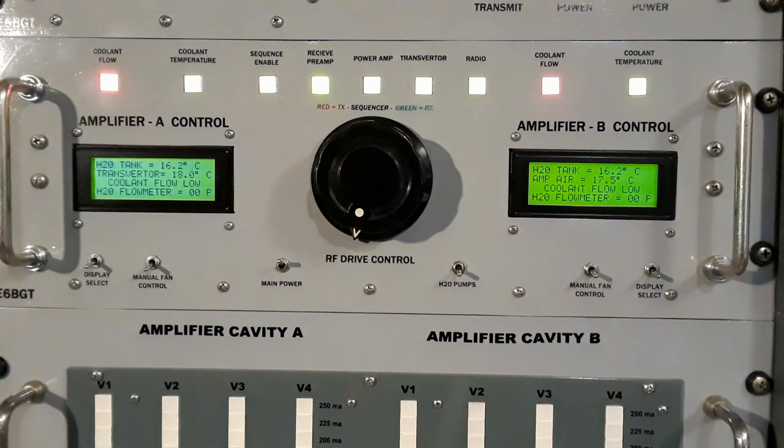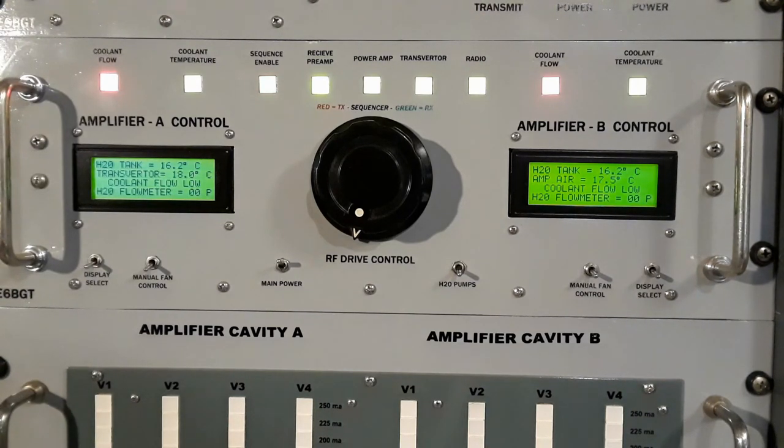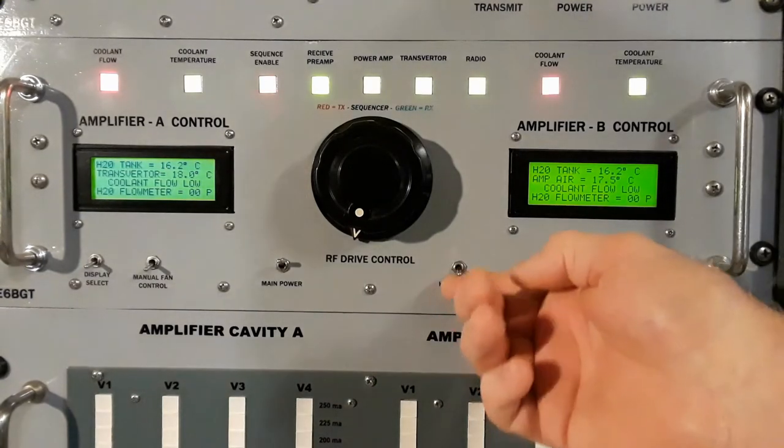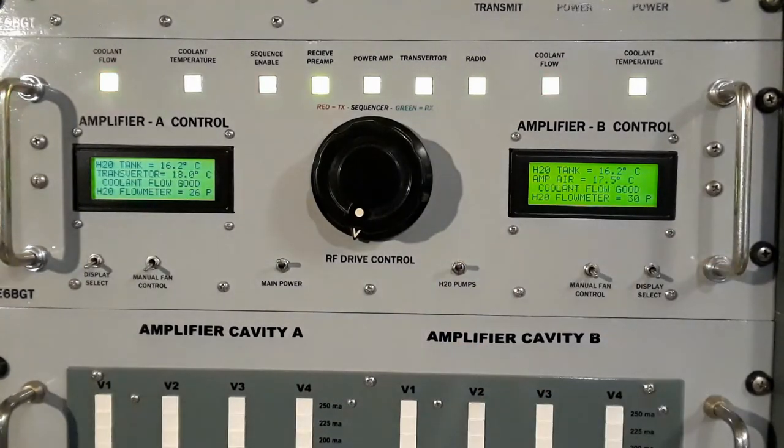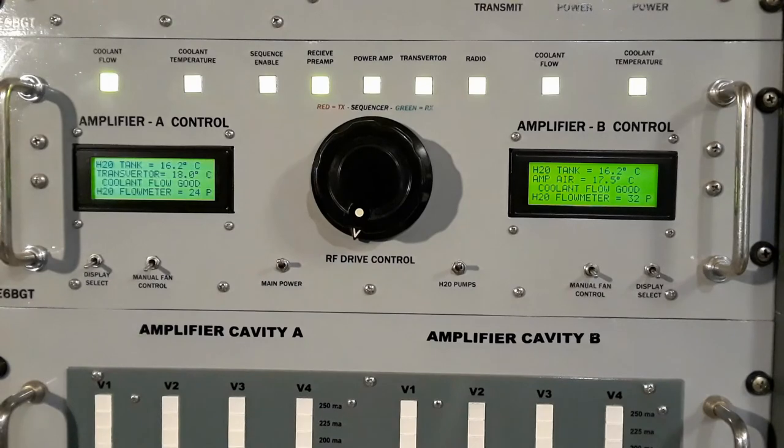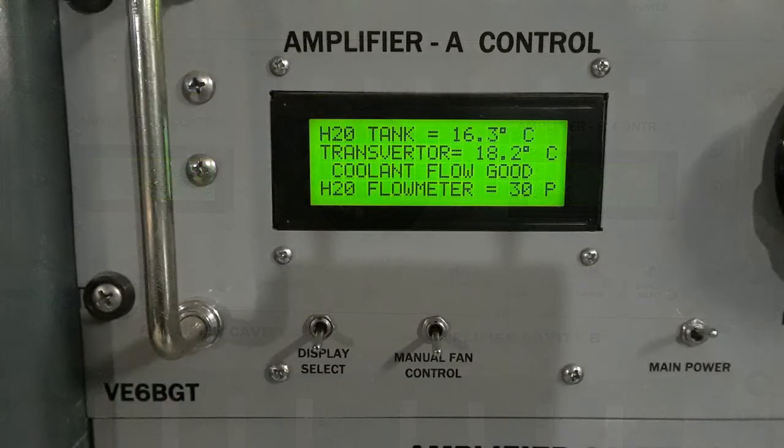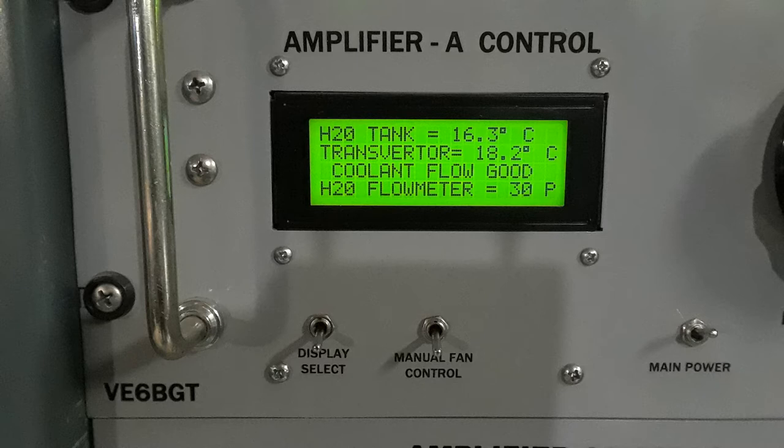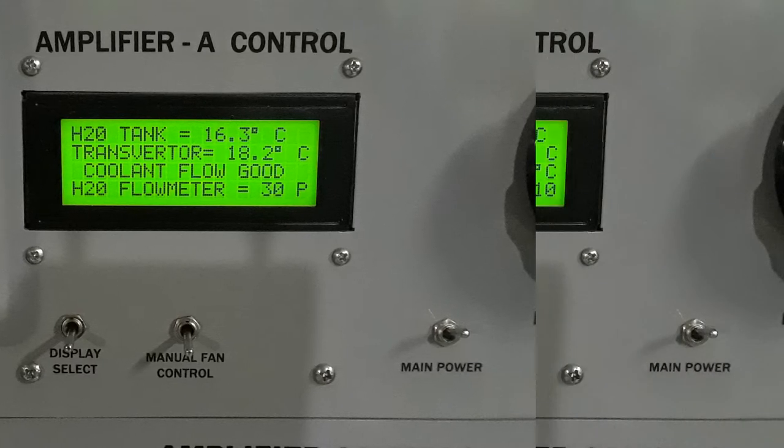Back to the main control shelf here. It's probably hard to see in this video, but when the pumps are turned off, the coolant flow LEDs were red. And also the sequence enable LED is flashing. And when everything goes green, the amp is ready to transmit. Looking at the LCD itself, the first line tells you what the water coolant tank temperature is. In this particular display, the transverter water temperature is next. And then the third line is telling you that the coolant flow is good. There's a set point that trips it. And then the bottom line is telling you how many pulses per second the flow meters are indicating.